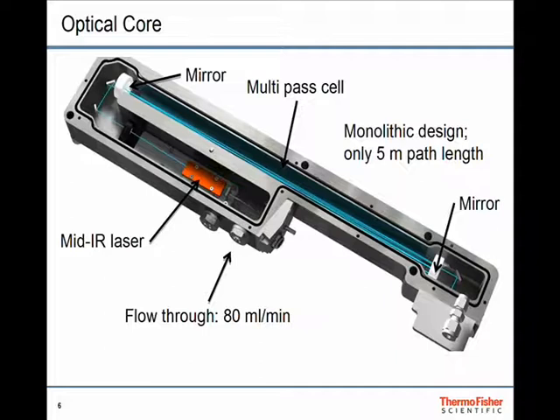These mirrors, something to note, are regular mirrors. You can actually see yourself in them, except they're slightly focusing, so your image is a little distorted. They also work if they're slightly dirty. If you have some contamination that may come into the cell here, the method will still work. You may decrease the precision a little bit, but it's not gone. There's no requirement for super-reflective mirrors in this setup. It's really a monolithic design. All these mirrors are glued in place using telecommunication technology. This is all very robust. You can shake it and nothing happens. There's nothing to adjust.